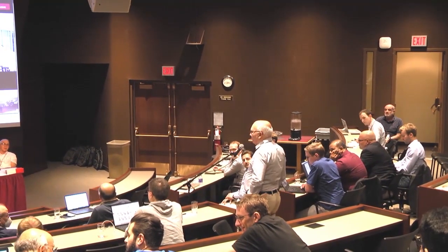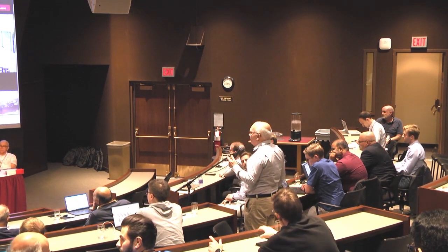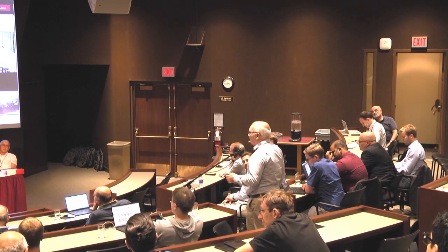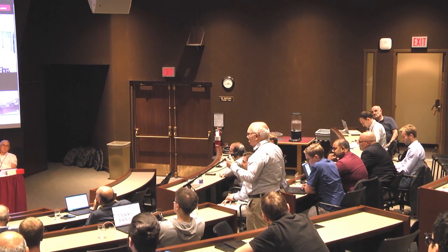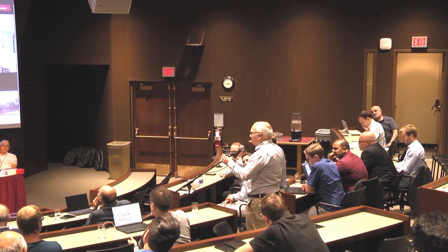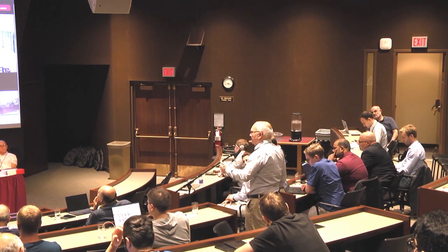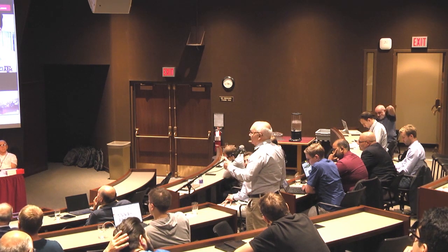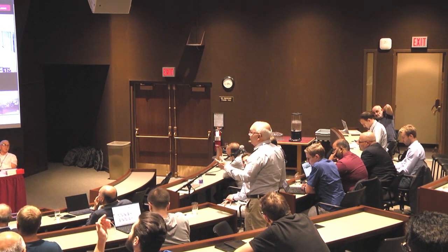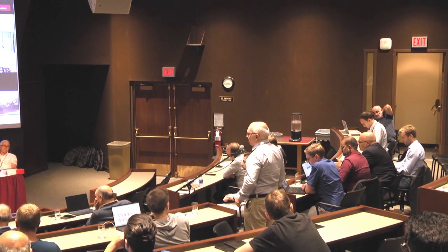Antonio Simões Costa, Federal University of Santa Catarina, Brazil. My question goes to you, Kumar. How will you compare your data-driven substation configuration identification methods with generalized state estimation? As a reminder, generalized state estimation started in the 90s, and it considers the through variables, power flows and currents, as additional state variables. Then it uses well-consolidated estimation methods to identify topology along with the conventional state variables. So what advantages would your approach have?